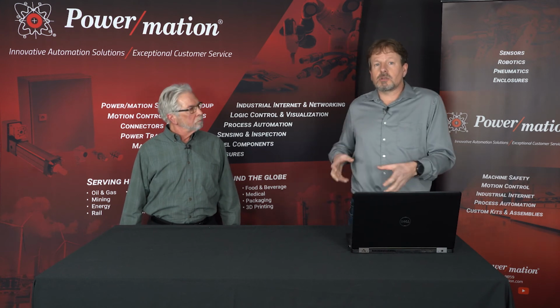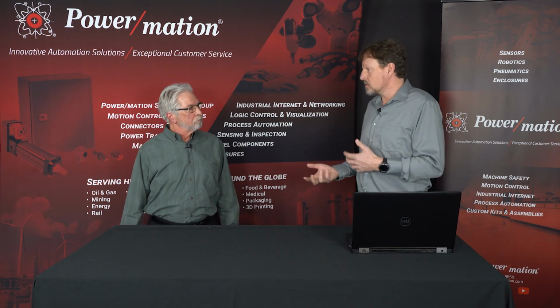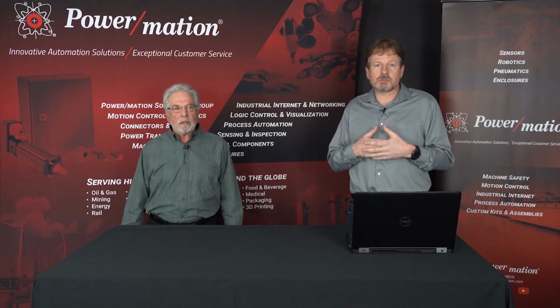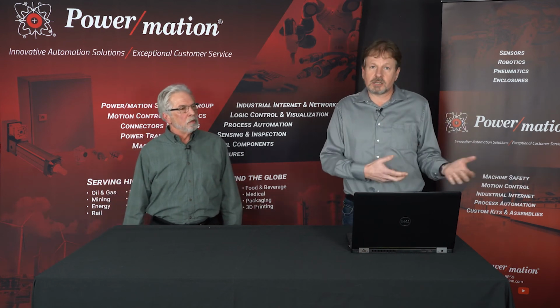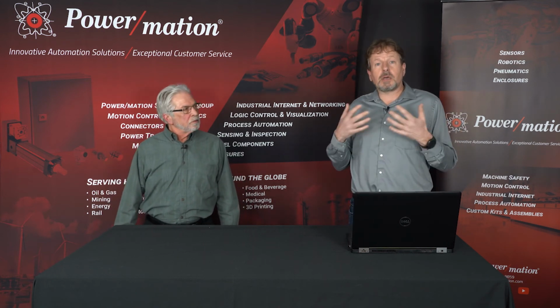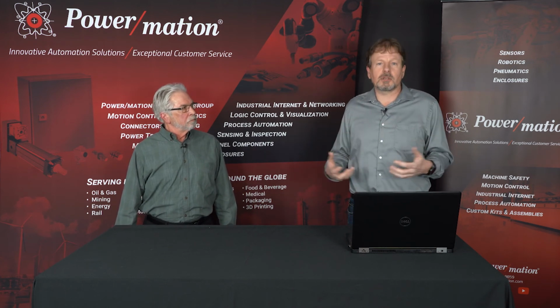Now, what we didn't talk about today, which is a bit more complicated, is the I/O itself. And so the I/O can become very, very complicated and very expensive. So you could bring in your I/O landing it to a single input card, and now you say, I need to double that. I don't trust my sensors. I want to have 2 sets of sensors. Maybe I want to have 3 sets, and I want to have a voting scheme. Those types of systems aren't really in the control space per se. Those are more in the actuation side of things and more in the detection side of things.